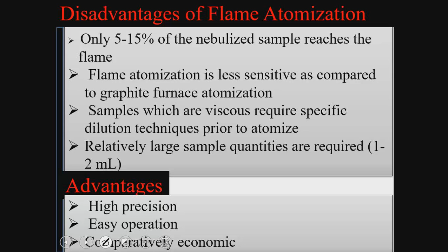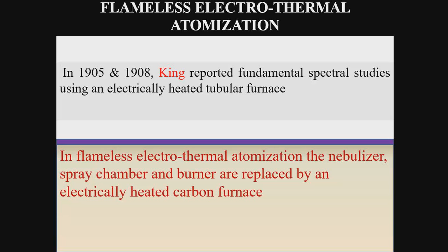To overcome the shortcomings of flame atomization, L'vov introduced another method using an electrically heated tubular furnace called flameless electrothermal atomization. In this method, the nebulizer, spray chamber and burner of the conventional atomic absorption spectrophotometer are replaced by an electrically heated carbon furnace. A graphite furnace is made up of a graphite tube which is open at both ends and provided with a hole at the center for sample injection.